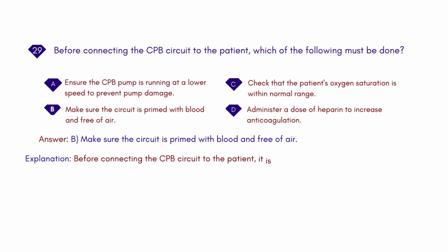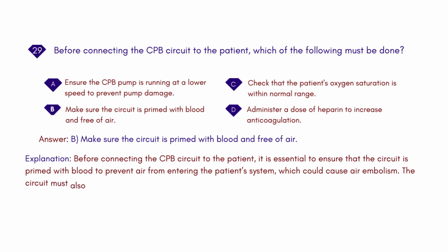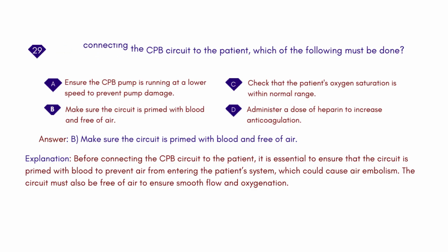Explanation: Before connecting the CPB circuit to the patient, it is essential to ensure that the circuit is primed with blood to prevent air from entering the patient's system, which could cause air embolism. The circuit must also be free of air to ensure smooth flow and oxygenation.